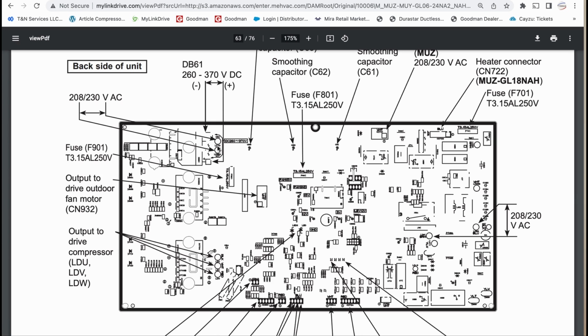Okay, but let's say you had voltage here and you wanted to check your DC voltage, your high voltage DC. You would physically go over to this little negative mark right here and positive mark, and you should get anywhere from 260 to 370 volts DC. Now that's going to be relative to what your incoming voltage is, what your 208, 230 is. So the higher your incoming voltage, the higher your DC voltage. Okay. So once you check your DC voltage, if you have it here, then good and fine. Let's move on. But if you don't have high voltage DC, but you have line voltage coming in, then we need to figure out what the problem is.